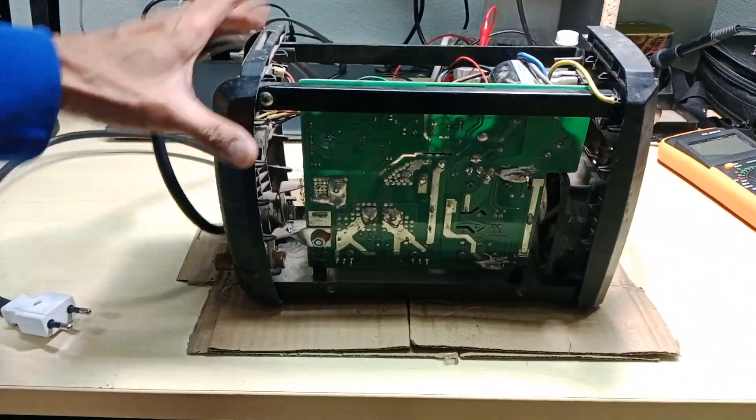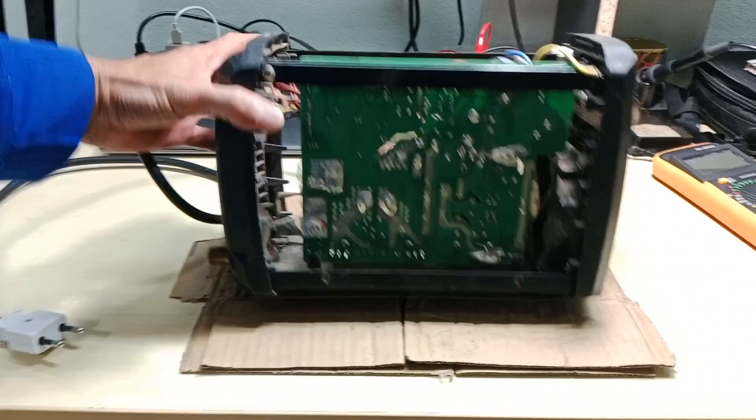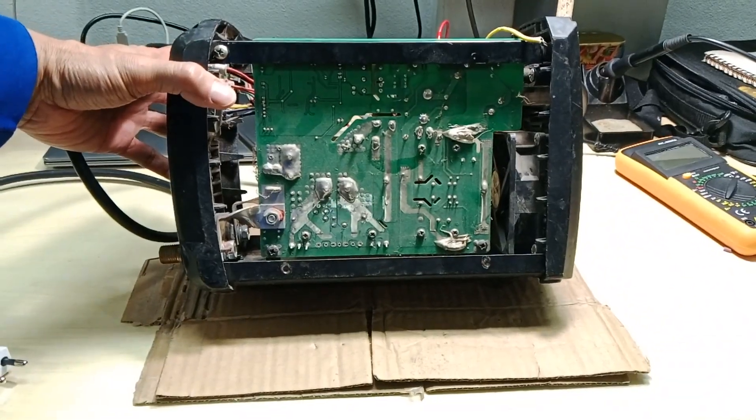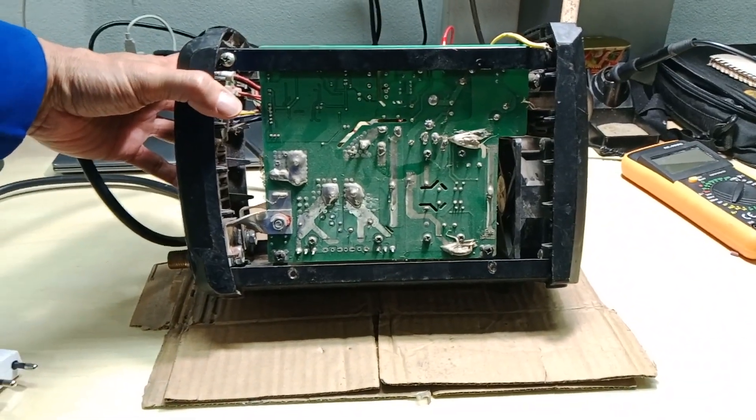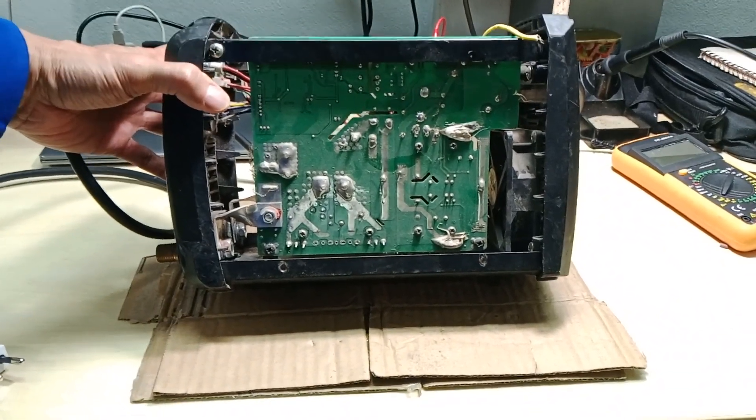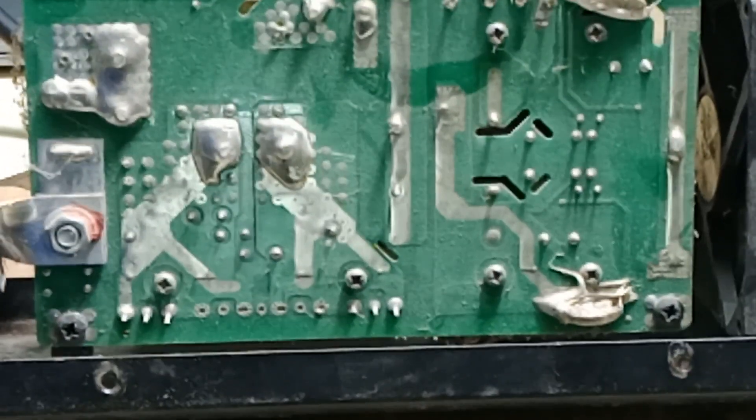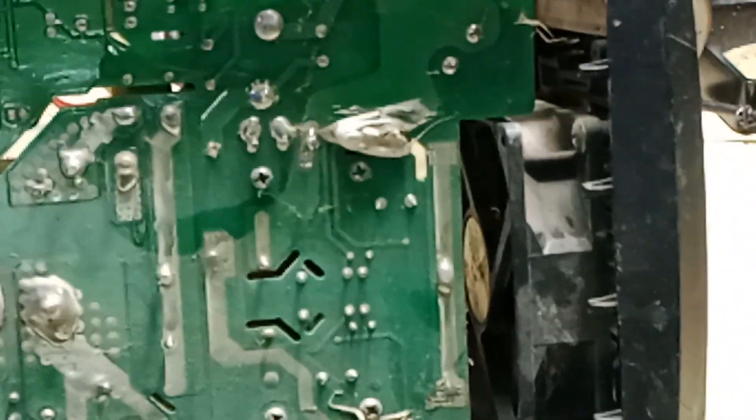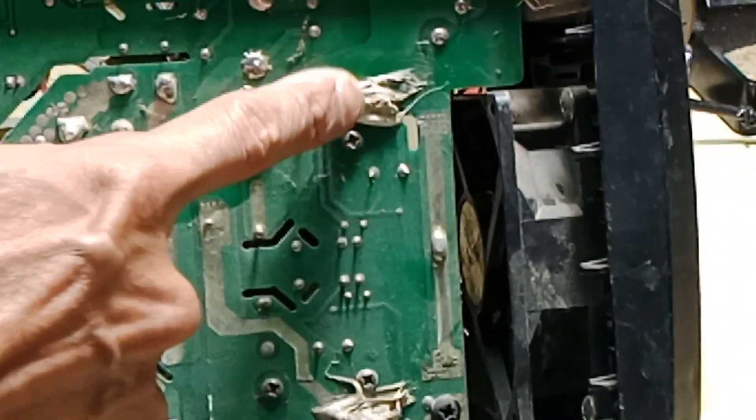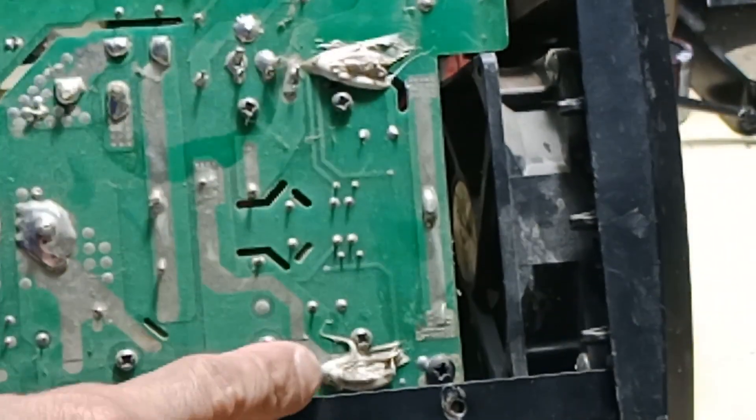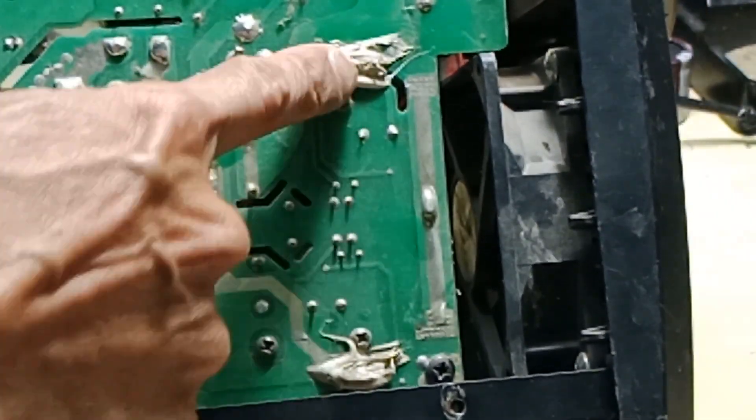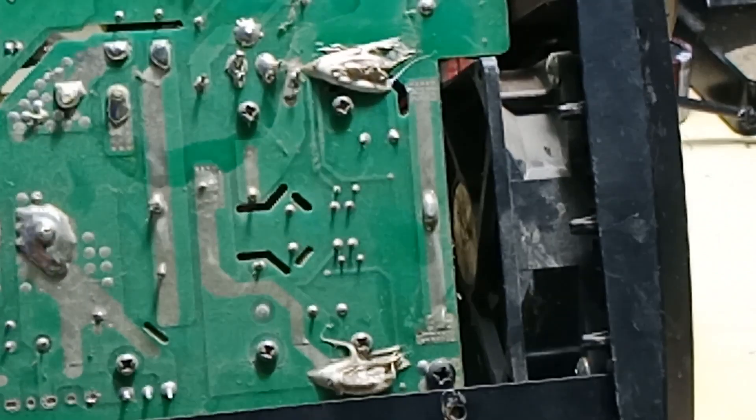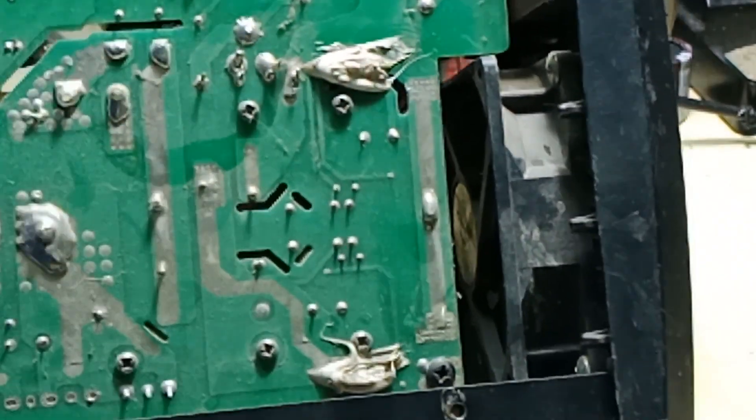In this case, our first suspect are the IGBTs. You can see that the manufacturer covered the IGBT terminals with some kind of insulating sealant. I have to remove those to test the IGBTs.